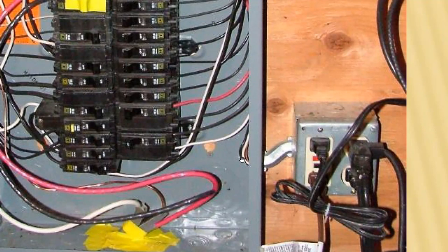So, to prevent that from happening, we are bonding the box, which means the grounding or bonding wire is going to be permanently mounted right to the box. So the box is grounded, or the box is bonded. What happens if the hot wire becomes loose now? If it becomes loose, and if it touches the metal box, the current will flow from the hot wire, through the box to ground.